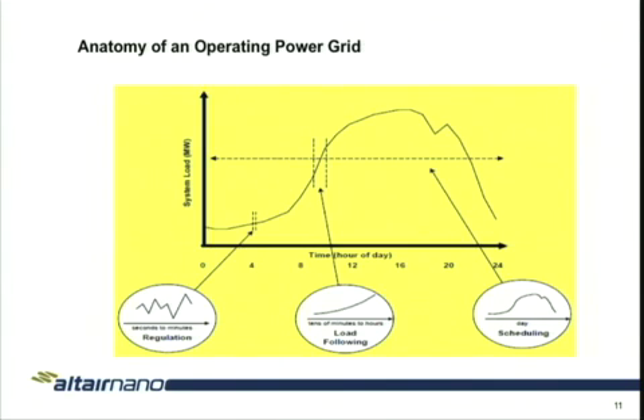Okay, but let's talk. Really, the talk is focused on the power grid, and if you think about what happens during the day and what your grid needs to do throughout that time period, you can talk about a small grid or you can talk about a large grid, but you have pretty much a base load that occurs during the evening. And then what happens is you start ramping up. You have your peak load during the day. Sometimes you have a notch as maybe commercial businesses are shutting down and people are heading home. Then you come back and the power offloads during the day. Well, how does that get taken care of? I mean, it just doesn't happen on its own.